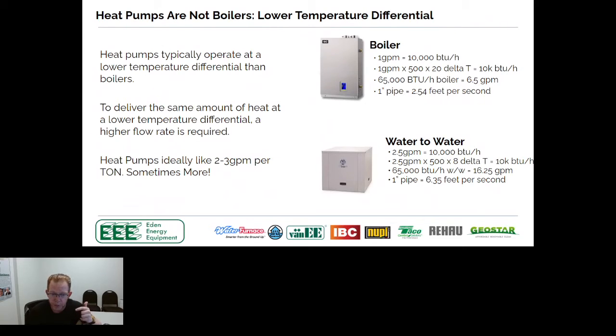So if you look at the bottom right-hand side, you can see how that ends up working out. Instead of a 20-degree delta T, we actually end up with a 5 to 8 degree delta T on our hydronic heat pump, which is where the 2 to 3 gallons per minute comes from, right? So if you look at the drawing, at my slide on the right-hand side where I refer to the boiler at 1 gallon a minute, we know the boiler can do a 20-degree delta T, so we know 65,000 BTUs is 6.5 gallons a minute.